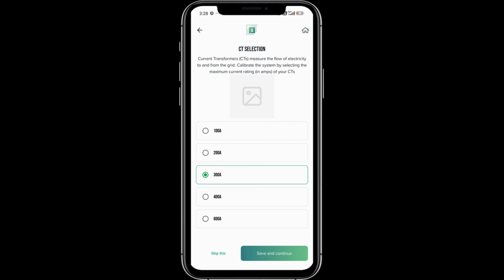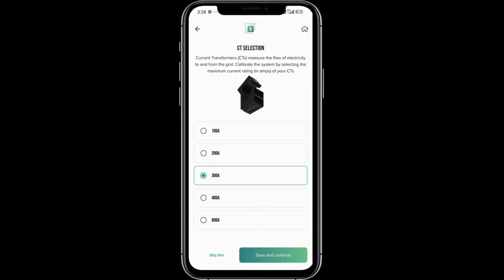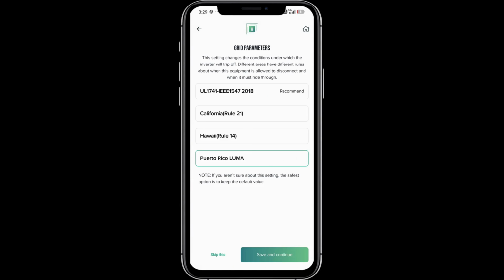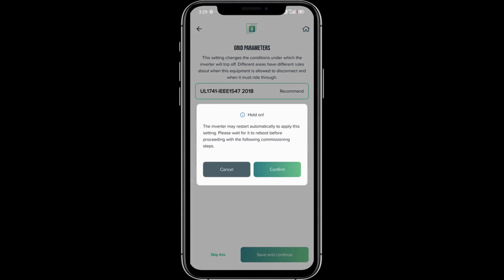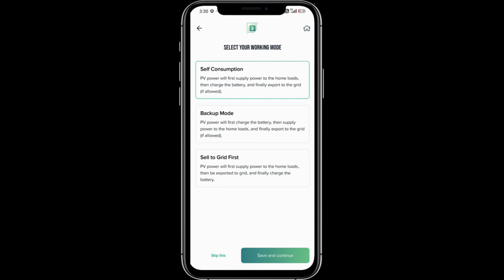All Envy series inverters come with a CT included. Since this is an Envy Duo, we will select the 300 amp rated CTs that are included with the inverter packaging. Note that this installation can support CTs anywhere from 100 amps up to 600 amps. Next, select the grid profile based on your region, and unless otherwise specified by a local electrician or authority, choose UL 1741 IEEE 1547. And after selecting the grid profile, the inverter will automatically reset to apply these changes.